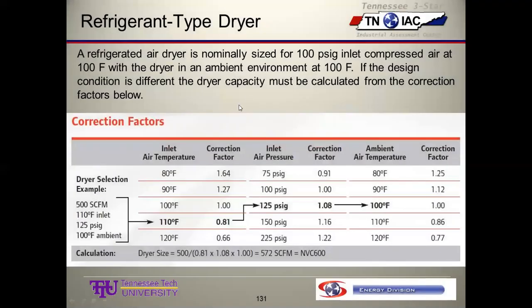Okay. Now, we said these dryers are nominally sized for 100 psig inlet pressure from the compressor at 100 degrees Fahrenheit, and sitting in an air compressor room that's 100 degrees Fahrenheit ambient environment. So we say these are rated for 100, 100, and 100. And so you see what those hundreds are. If the design condition is different, it's going to affect the dryer capacity and must be calculated using these correction factors below. So we have a little example here.